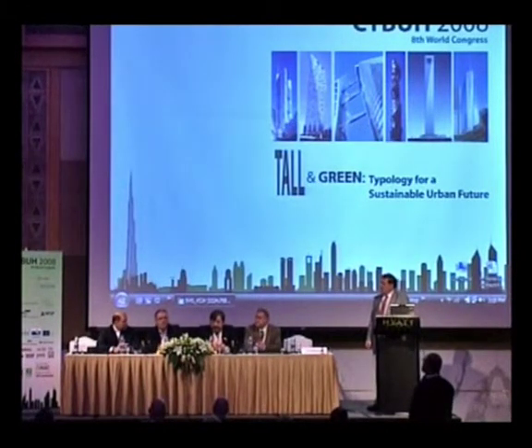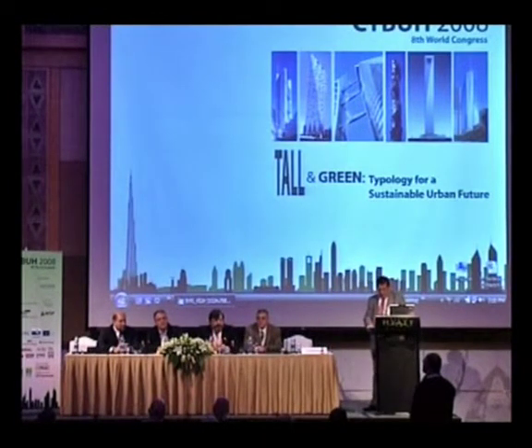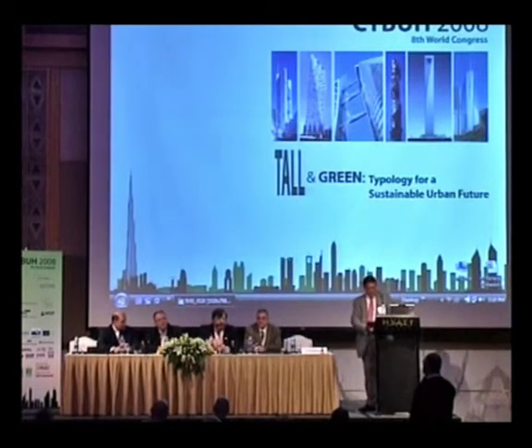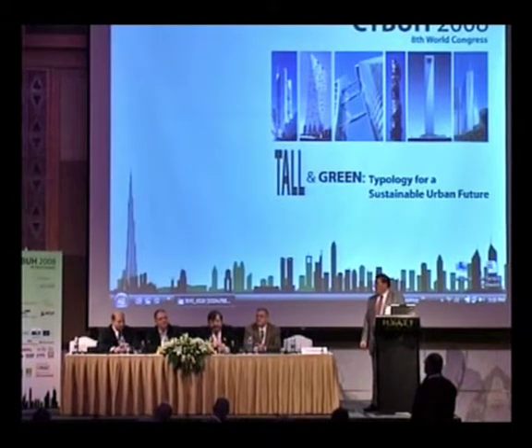In some of the single-stair buildings we look at, we are looking at pressurization, but generally we're using systems which achieve similar effects but aren't pressurization. For example, the Beetham Tower uses a mechanically assisted natural ventilation solution to the lobby, which is a shaft with a pressurizing duct that feeds air in. We don't use the word pressurization because they're engineered solutions. If you say pressurization, it means you're designing to a specific code, which is there for specific reasons. When we're engineering these solutions, we tend not to use the word pressurization. So we have a number of different options which achieve a similar level of protection as pressurization.